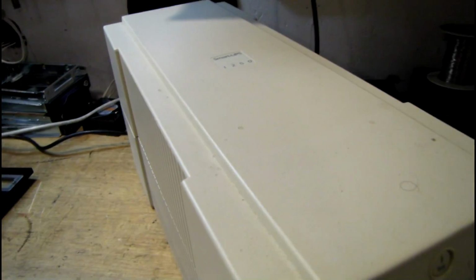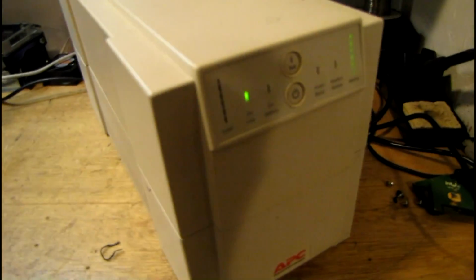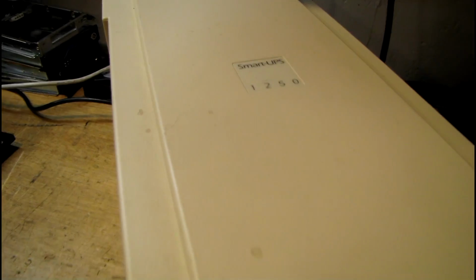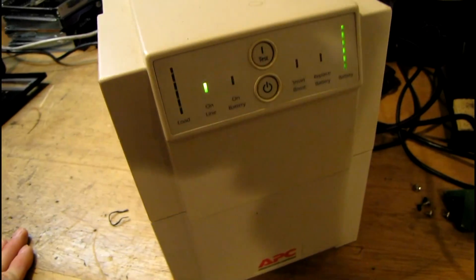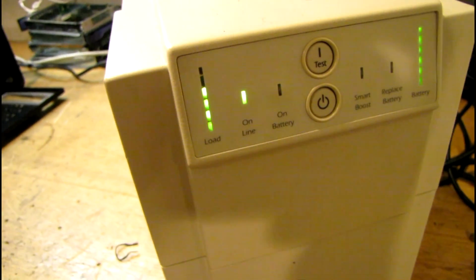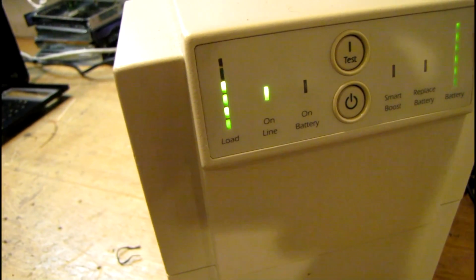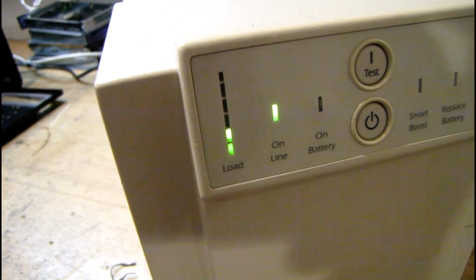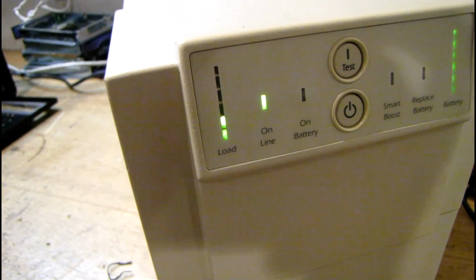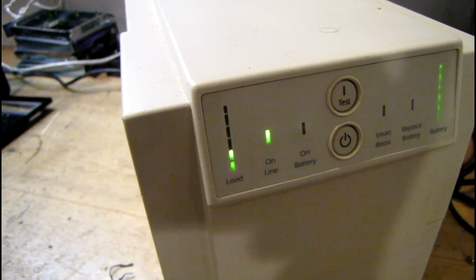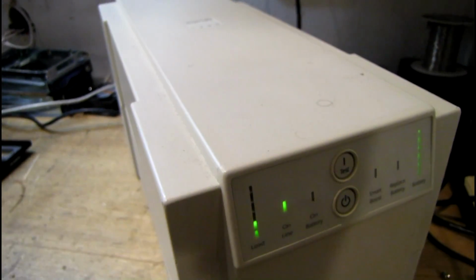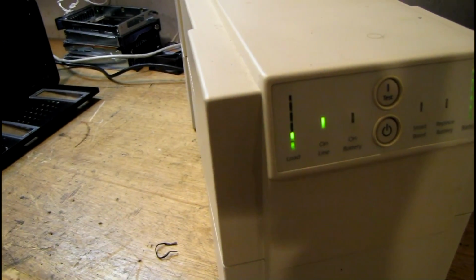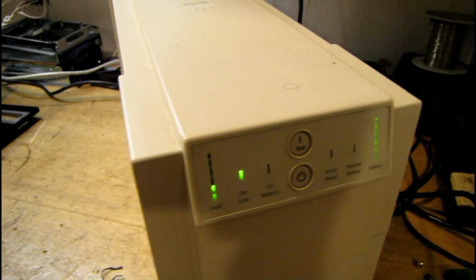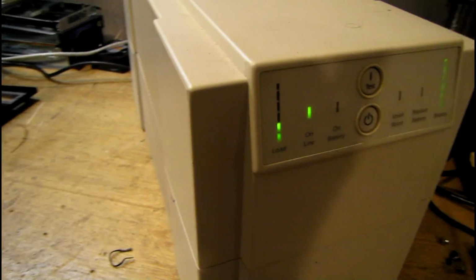Now this is a 900 watt rated UPS, 1250 volt amps. Let's see how much current this server pulls when it spins up the hard drives. Holy crap. Yeah, it's up there pretty good. That's probably about 600 or 700 watts there for a little bit. And it looks like it's going to settle back down at around 250 or 300.